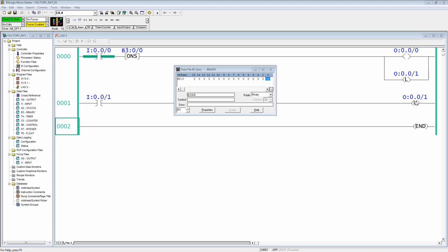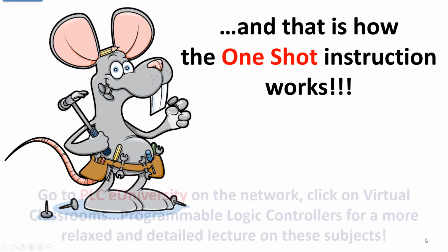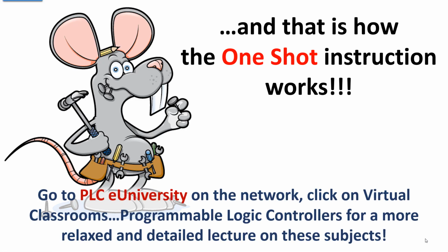Keep in mind this bit trap. This is an excellent troubleshooting tool when you're working with logic on the shop floor and you look at the rung and you can't tell if it ever went true or not. Throw in a bit trap. You can use any unused bit in memory and you will be able to verify whether the rung did or did not actually go true. And that is how the one-shot instruction works.